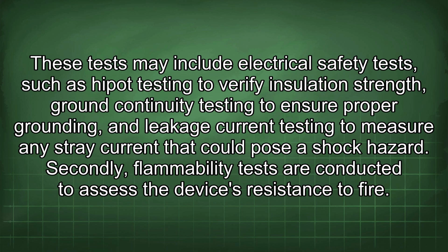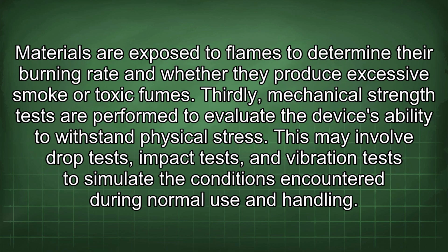Secondly, flammability tests are conducted to assess the device's resistance to fire. Materials are exposed to flames to determine their burning rate and whether they produce excessive smoke or toxic fumes. Thirdly, mechanical strength tests are performed to evaluate the device's ability to withstand physical stress. This may involve drop tests, impact tests, and vibration tests to simulate the conditions encountered during normal use and handling.